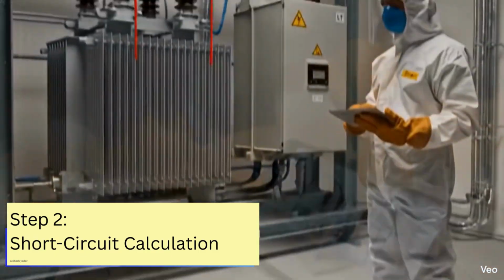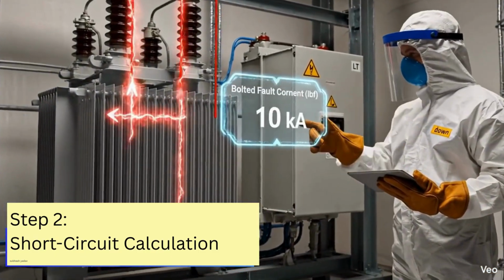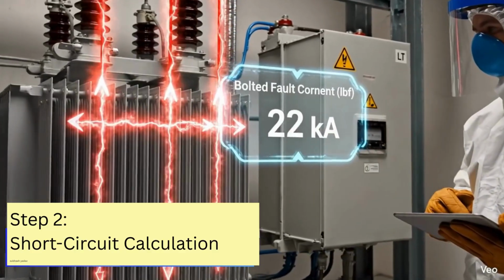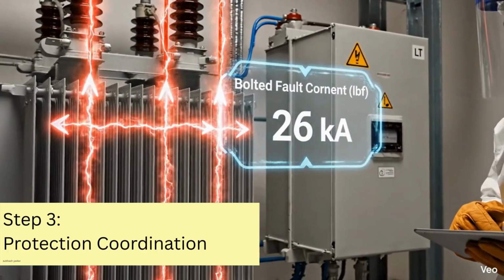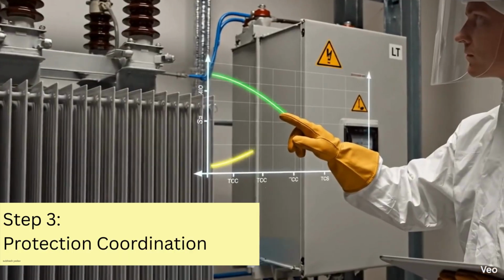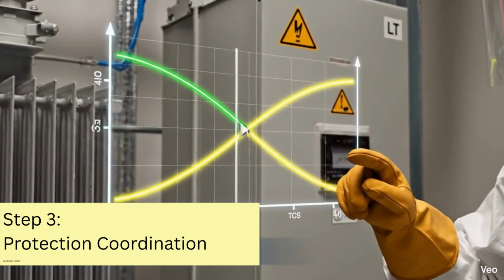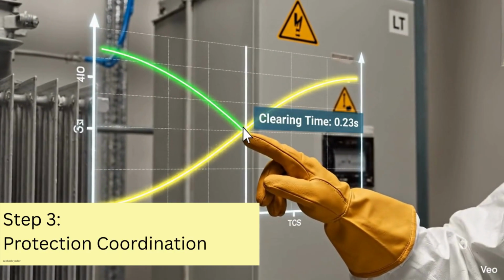Next, the short circuit current is calculated. This fault current is the base input for determining arc flash energy. Protection coordination shows how fast breakers trip. Clearing time directly affects the arc flash energy.